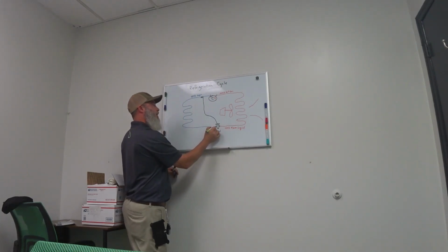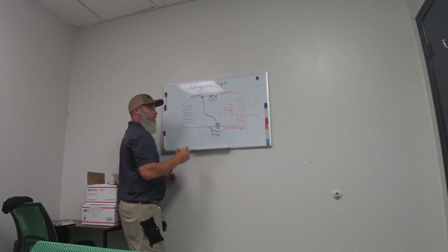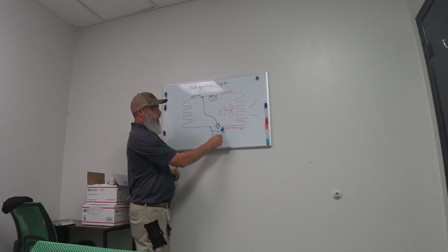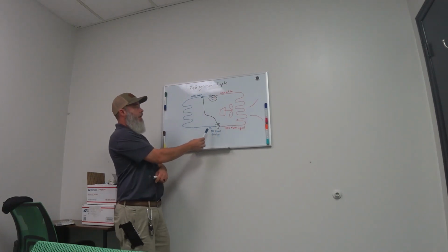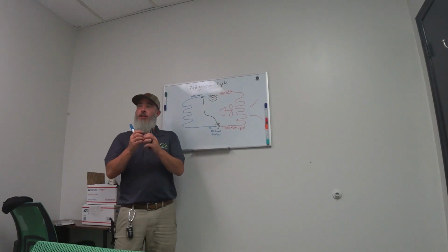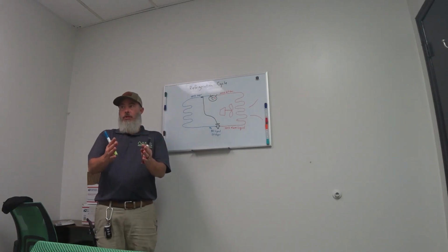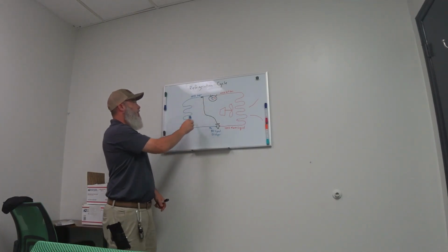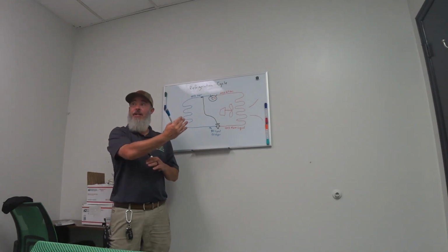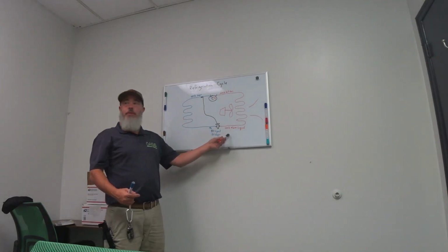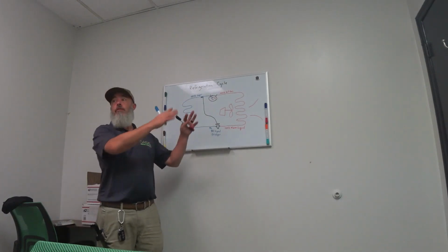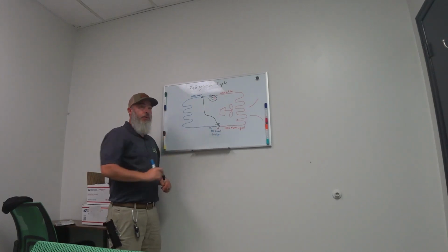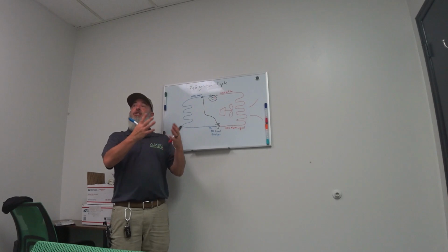Right here, at this point. Okay? So what's happening is that high pressure warm liquid is now coming out in a low pressure container, let's call it. This evaporator is a sealed system, so it's like in a container. So when that warm liquid comes out, it boils off. It's actually boiling because the pressure is so much lower that liquid is actually going to change state.